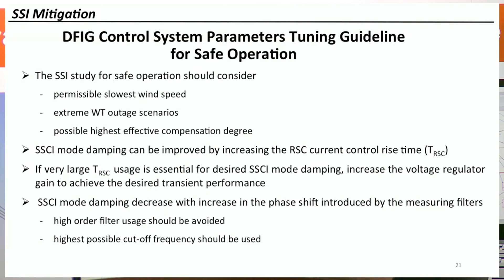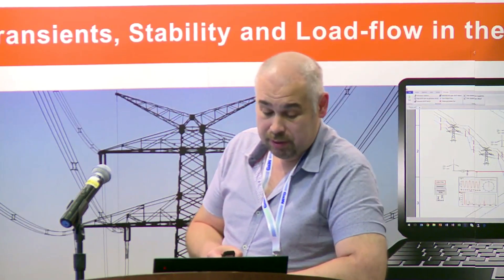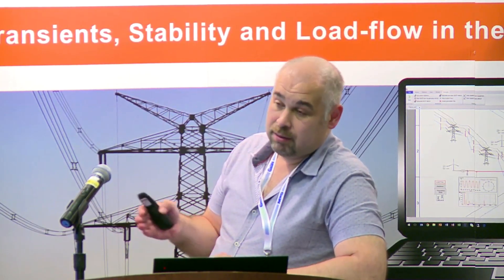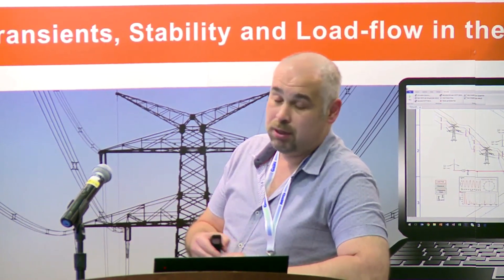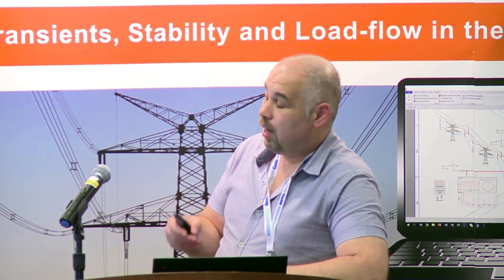For measuring filters, it is advisable to avoid high-order filters and select the highest possible cutoff frequency. This depends on sampling frequency and system constraints. Regarding fault ride-through requirements, the minimum reactive current during severe voltage sags or swells must be maintained. If we increase the rise time but also increase the voltage regulator gain, the reactive current remains above the initial value, satisfying grid code requirements.